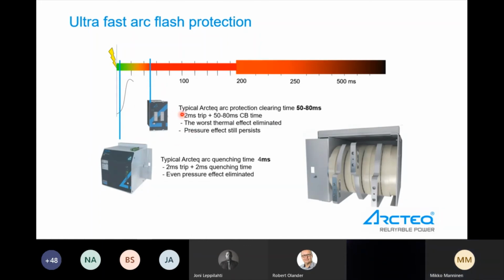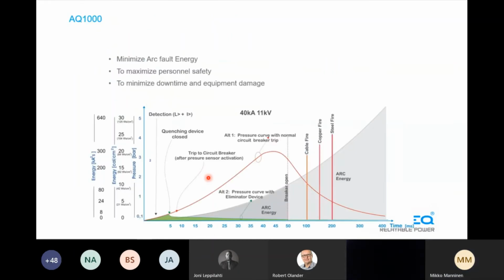So arc flash protection without quenching is still active very fast. It's around 7-8 milliseconds tripping time, and then the breaker delay, and then this AQ1000 will activate in 4 milliseconds. It will quench in 4 milliseconds. And these are just similar curves, but the idea is to activate in a very short time to eliminate the pressure and eliminate the damage to the board and to the personnel.